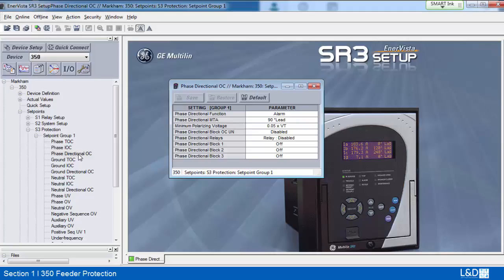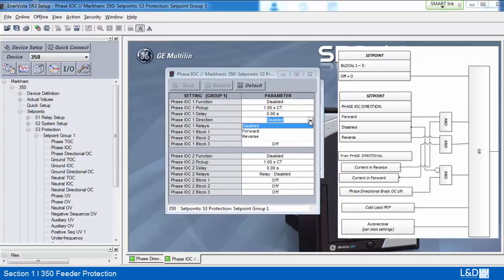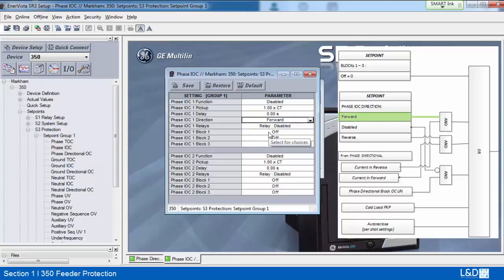Phase directional overcurrent is used to discriminate between faults that occur in the forward direction or in the reverse direction. The phase directional element can be used either individually for control or alarm by energizing the auxiliary output relays, or as part of the phase IOC or TOC element to define the tripping direction. For example, in the phase IOC element, when the direction is set to forward and the actual direction is reverse, then blocking will be on. The same principle applies to reverse settings and conditions.